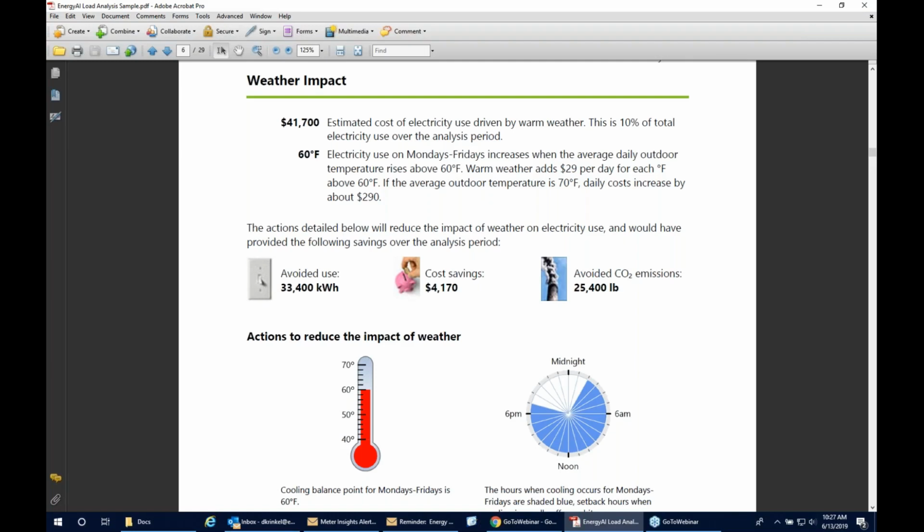So you might have a facility which its similar days of the week might be Sunday, might be one all by itself. You might have Mondays, Tuesdays, Thursdays, Fridays act the same, Saturdays act differently. So we will do the correlation separately for each of those. And we do it on a daily basis. So I know with metrics, typically you're doing it with billing periods. So you're doing it on a monthly basis. We actually will look at each day, average outdoor temperature for that day.